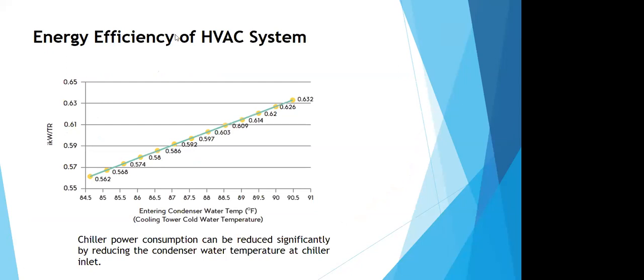Here we see this graph whereby we are trying to map the performance of a chiller with respect to its incoming condenser water temperature. If you look at a chiller which is operating at a condenser water inlet temperature of say 90 degree Fahrenheit, we are close to around 0.62 kilowatts per ton energy consumption. And if you're able to bring this down to say 85 by using a low approach cooling tower, we come to around 0.56 kW per ton. So we are saving almost 10 to 12% in energy by simply reducing the condenser water inlet temperature with the help of a low approach cooling tower.